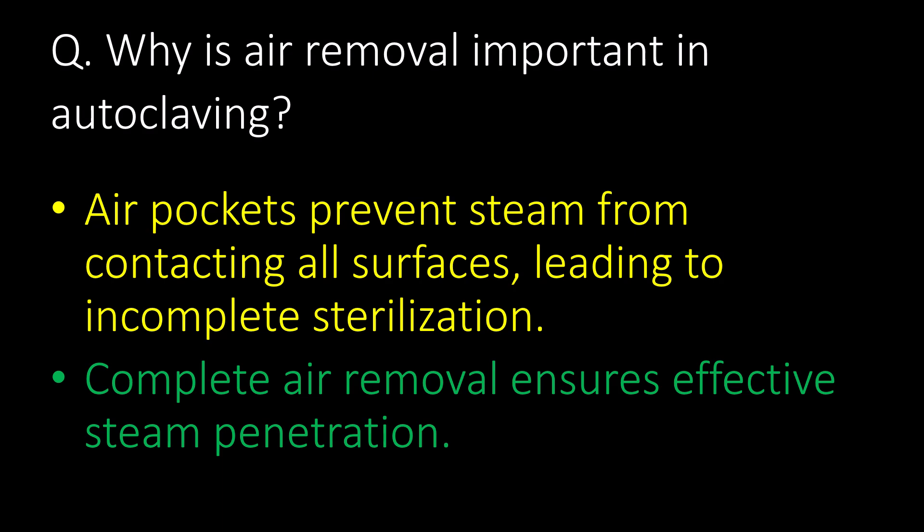Why is air removal important in autoclaving? Air pockets prevent steam from contacting all surfaces, leading to incomplete sterilization. Complete air removal ensures effective steam penetration.